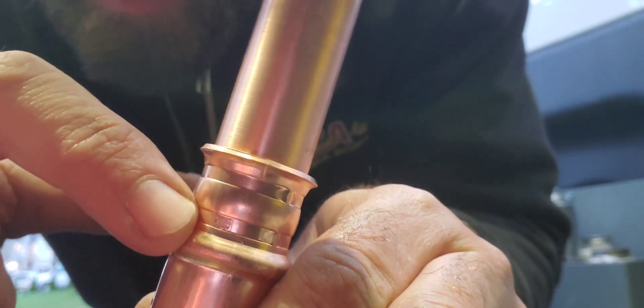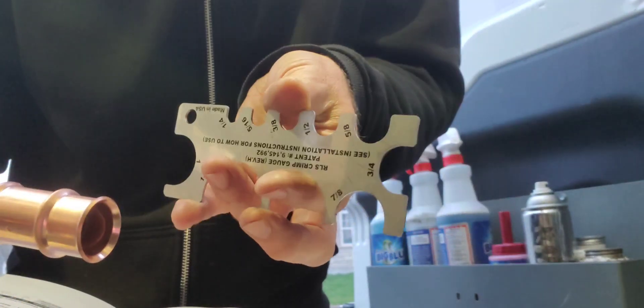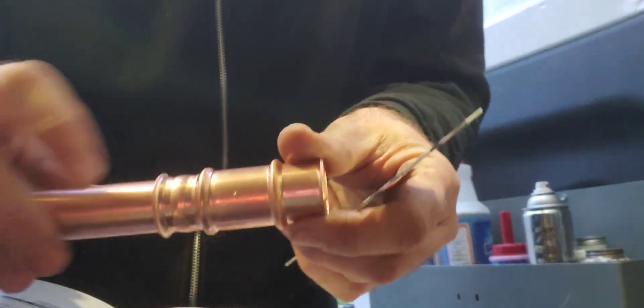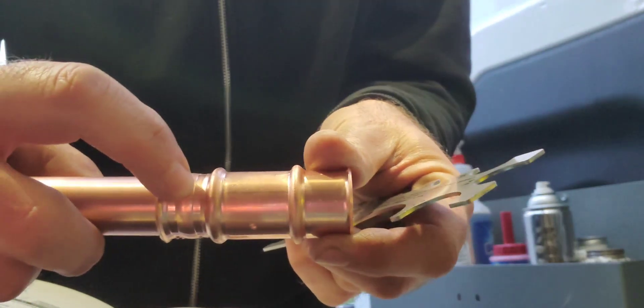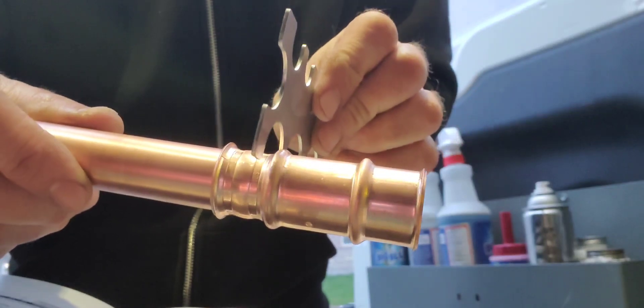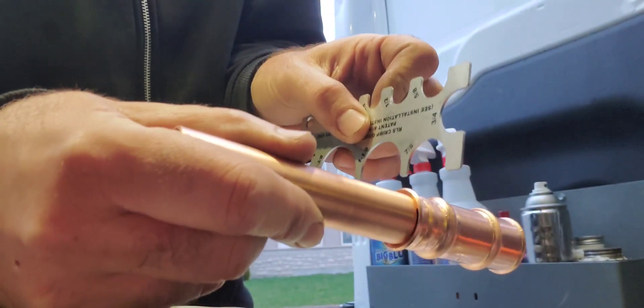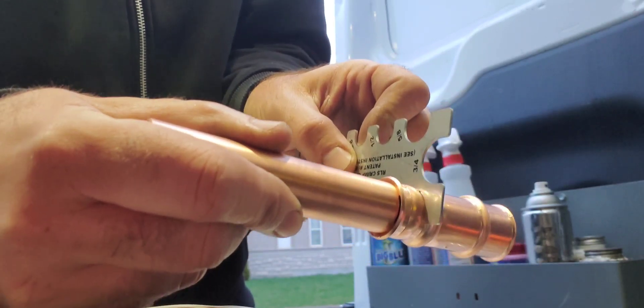I showed you where the RLS stamp was, which is right here. What you do is you take the crimp gauge for 7/8 and stick it on there. Now that fits on there nicely. If that doesn't fit on there, it's under-crimped and you're going to have to do it again.